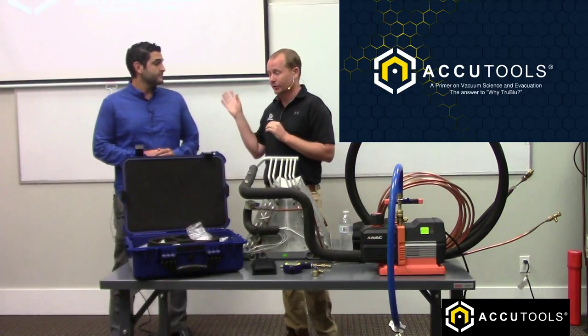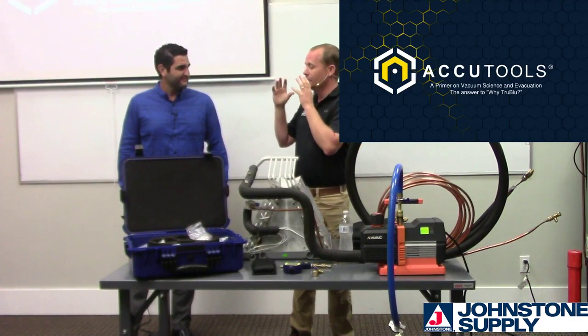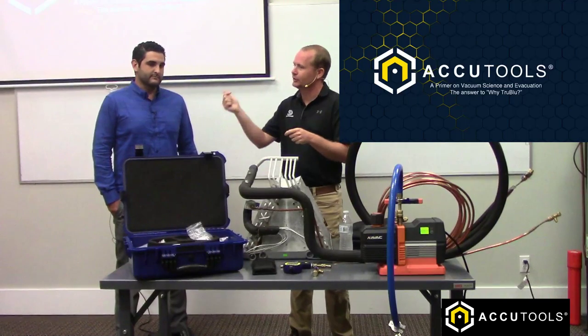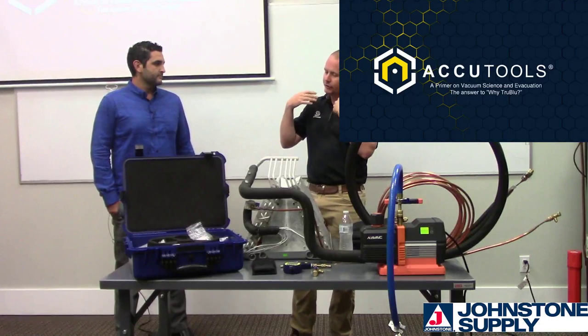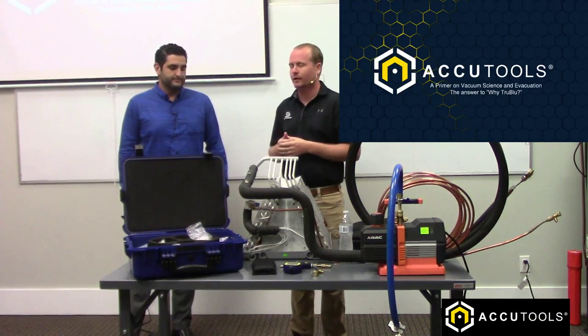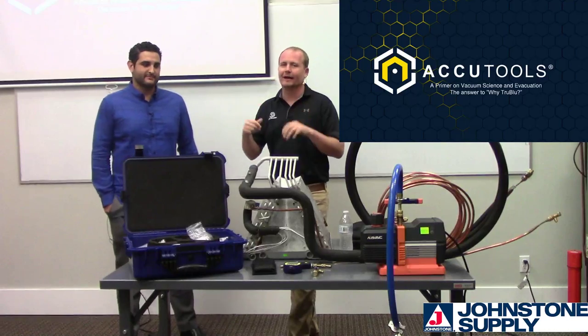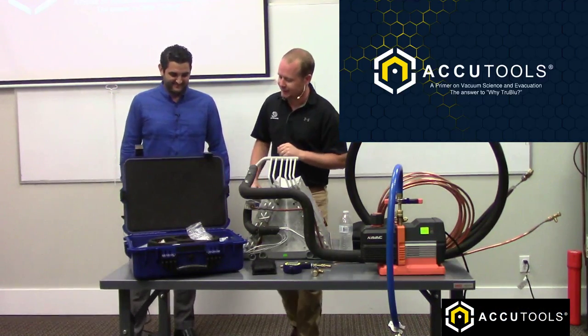Before going into the science of vacuum, I want to be really clear: using fancy tools and great processes is important, but common-sense practices are the biggest thing you can do for a good result. Things like not getting dirt in your copper lines when reaming, keeping everything capped until ready to use, and flowing nitrogen while brazing - these are all directly related to evacuation outcomes. If it's raining, don't leave tubing open. I've seen guys pull evaporator coils into the yard, hose them off, and never cap the copper lines. Common sense rules supreme here.